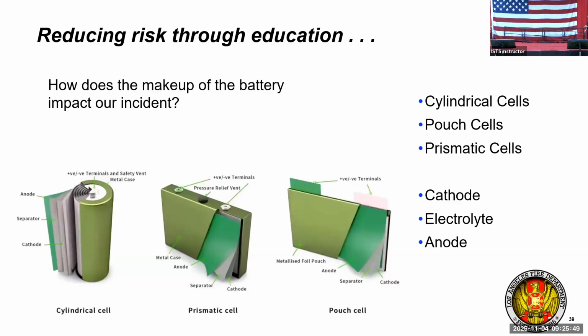The nickel-manganese-cobalt, you'll find those in EVs, particularly in e-mobility devices as well. Those are the ones that are our challenges, because during the decomposition of the electrolytes in there, it creates an oxygen environment. That oxygen that's getting released is what causes that intense fire growth, that prolonged burning event, which then requires an exorbitant amount of water to be applied, with a long, prolonged extinguishment.